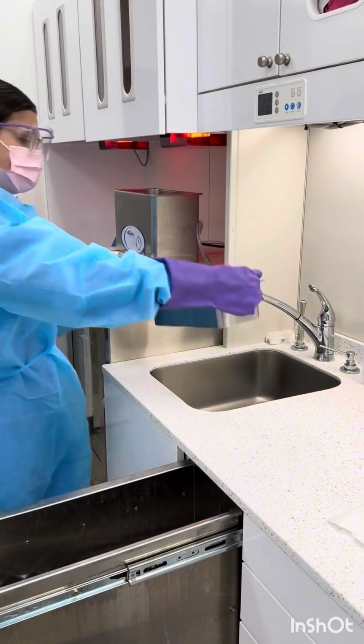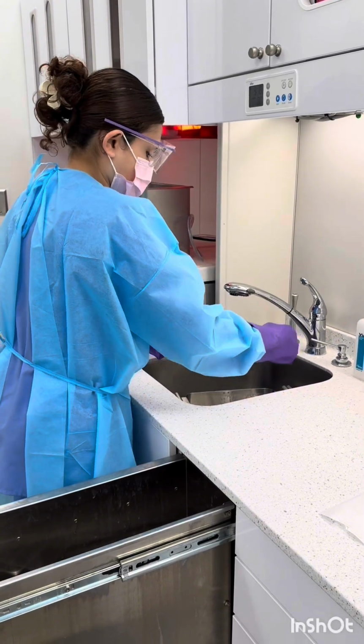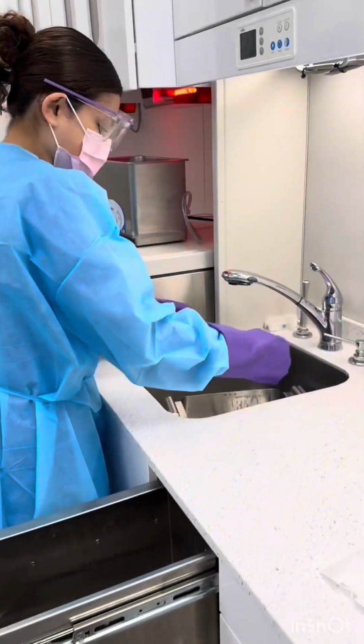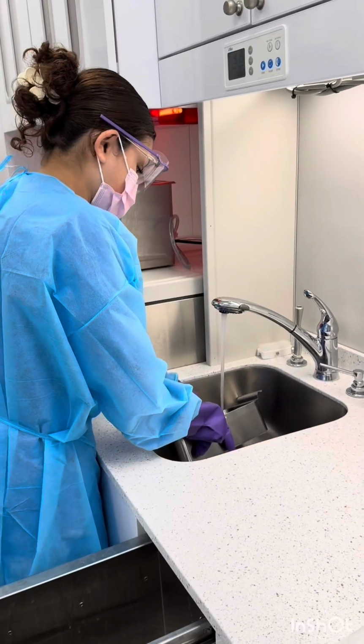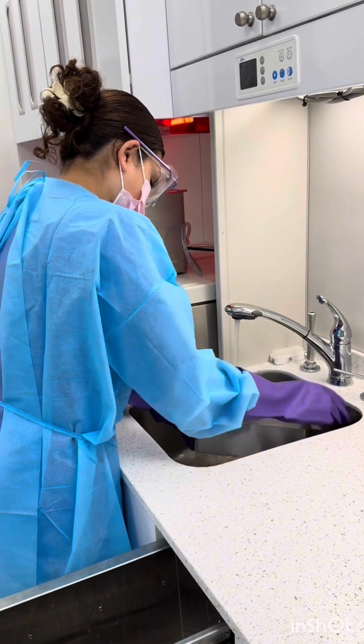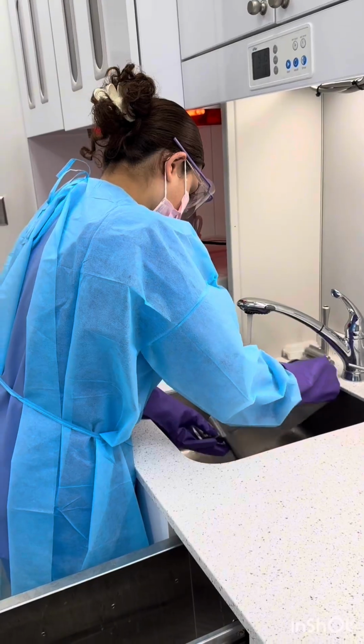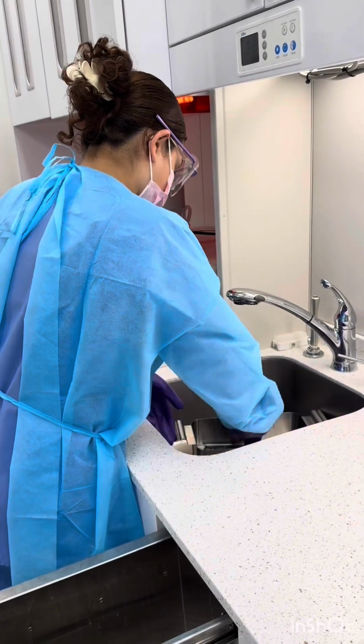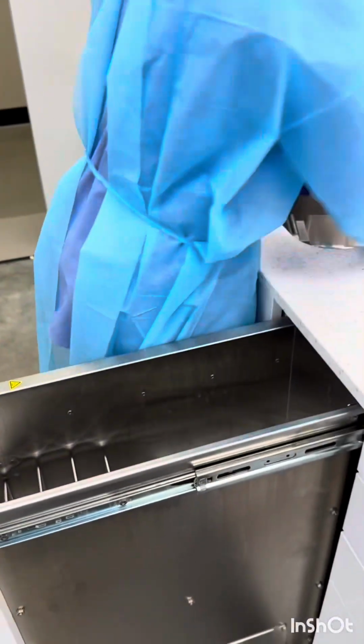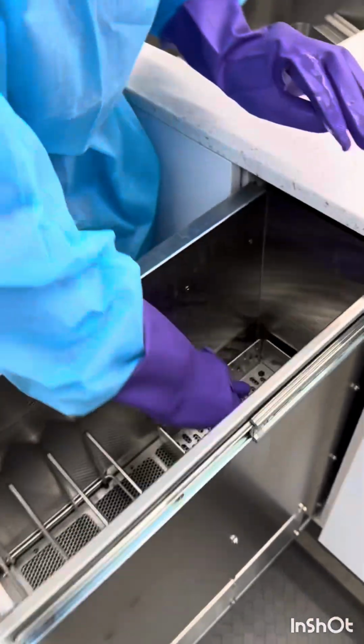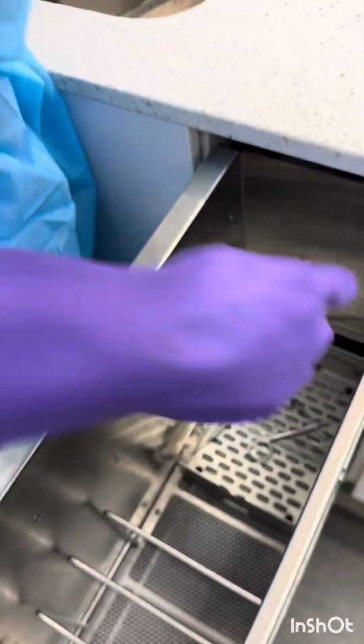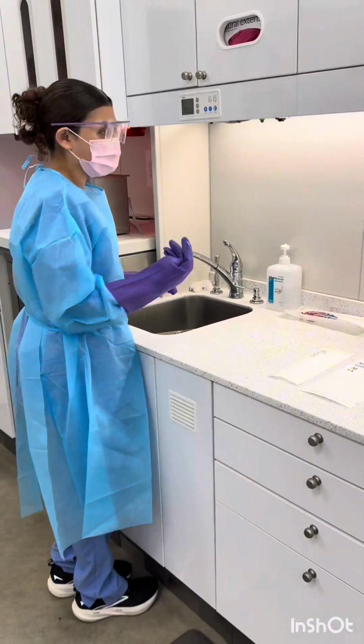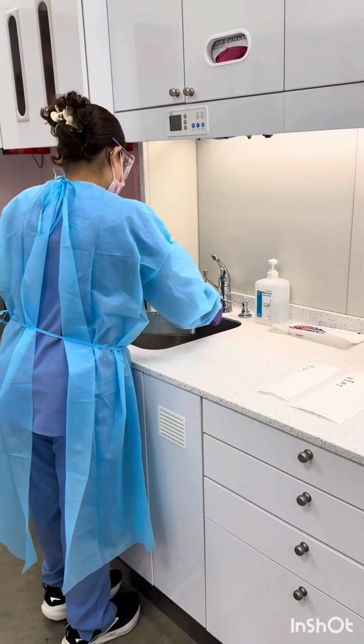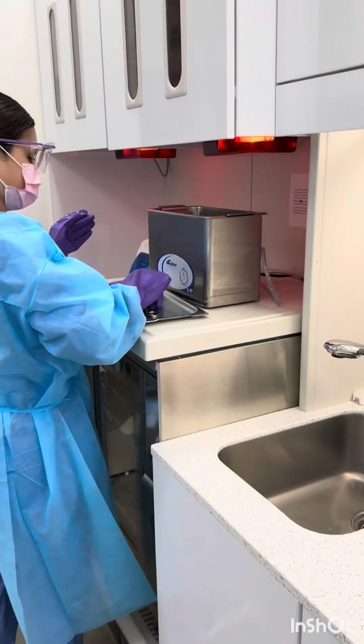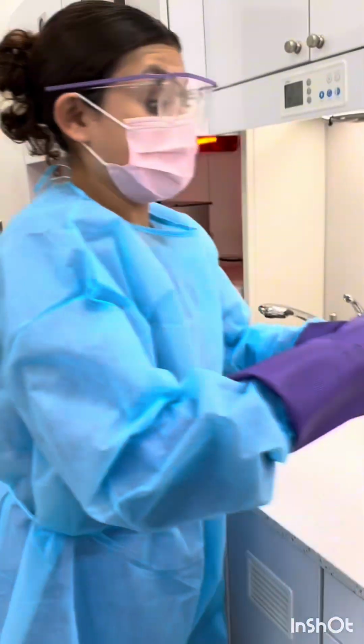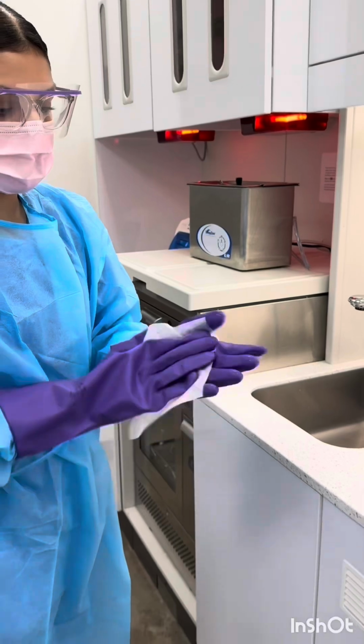Once the ultrasonic has run, loose instruments will be removed from the ultrasonic and rinsed under water to remove any leftover cleaner, and we'll place them in the dryer, which runs for 5 minutes. It is important to dry them to avoid any corrosion and wicking of the pouches. To start the dryer, wave your hand underneath the sensor. Again, be sure to wipe down your utility gloves after each use to avoid cross-contamination.